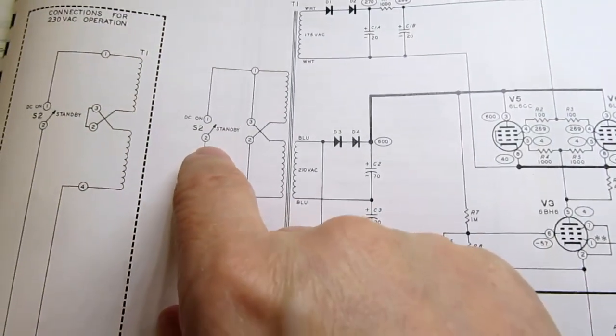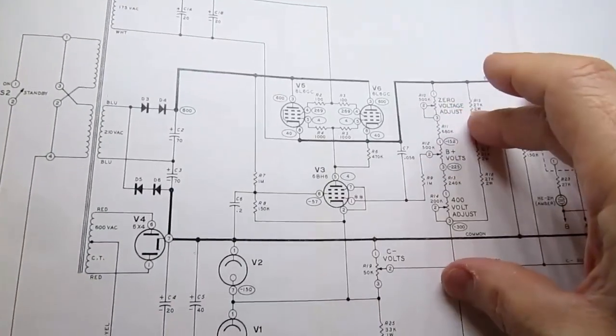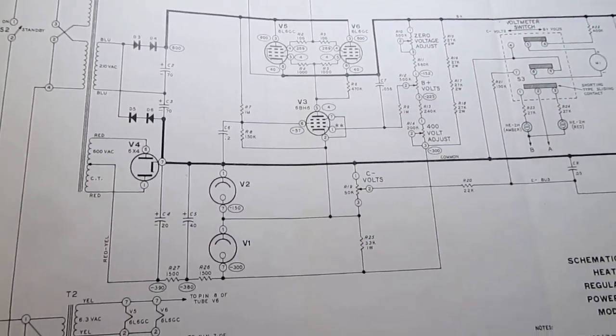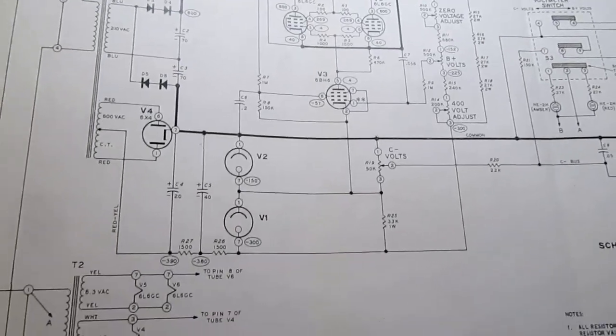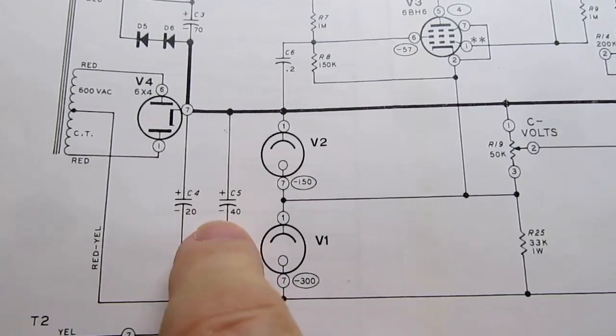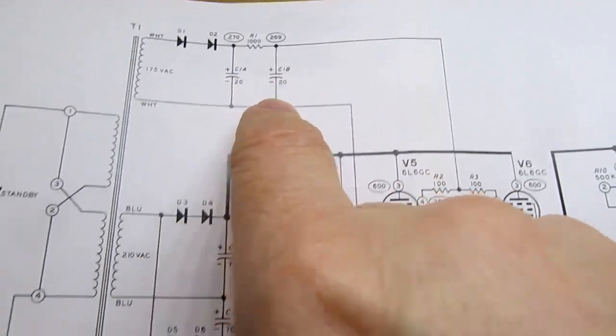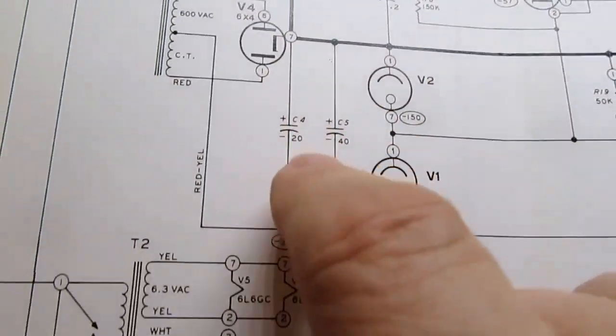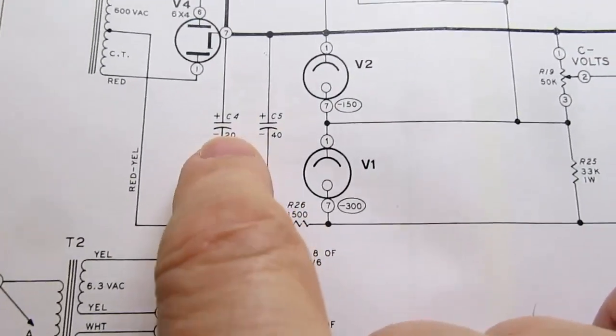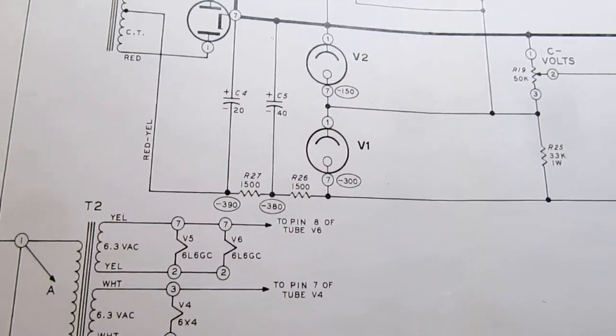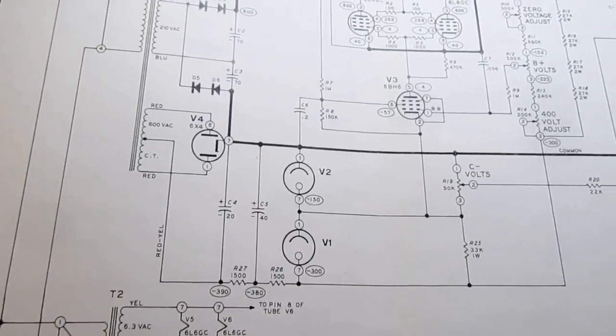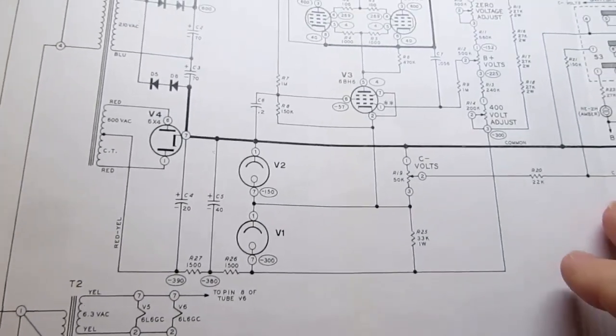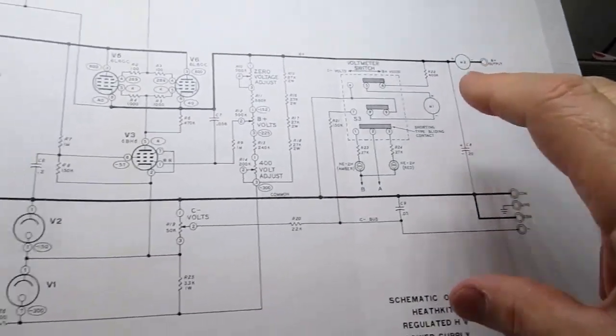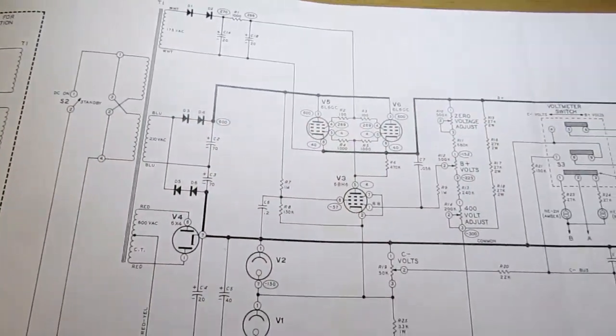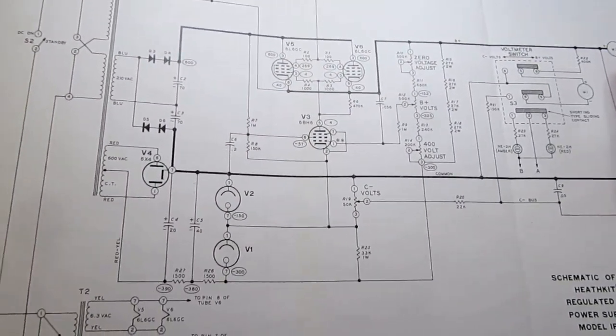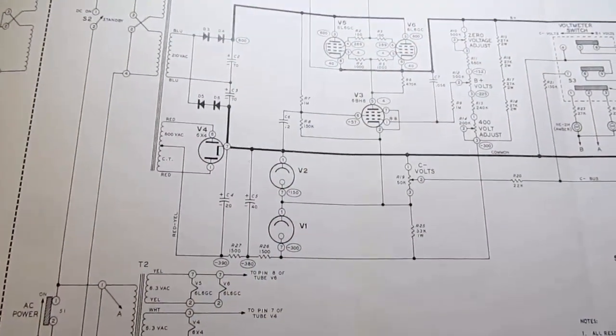As soon as you throw the standby switch on, then power is applied, and this immediately comes online. And you'll notice that there are essentially no capacitors in this circuit. There are a couple of little dinky capacitors down here, a couple of dinky capacitors up here, only 20 microfarads, only 70 microfarads, only 20 and 40 microfarads. So high voltages, but pretty small capacitances. None of those can provide substantial power for any length of time to the output loads. And that's why when you throw the switch here, it's presumed that the output goes dead right when you throw that switch. And when you turn it back on, it comes back up in a split second.